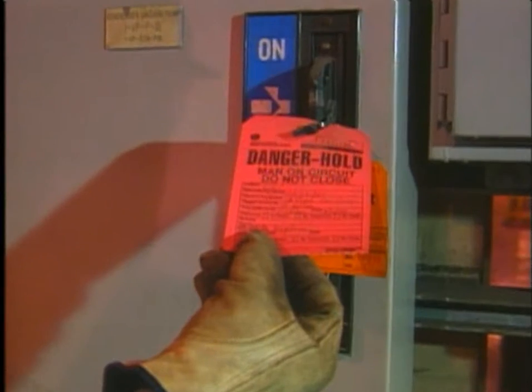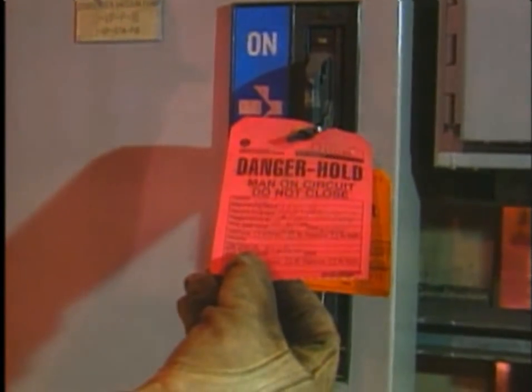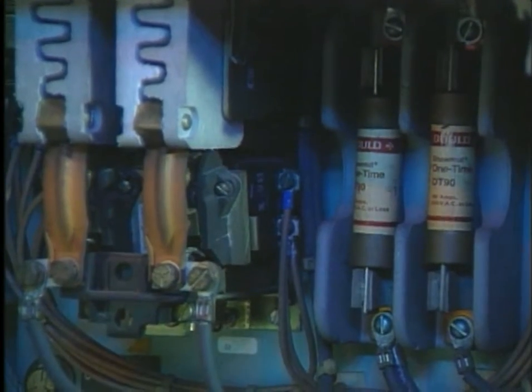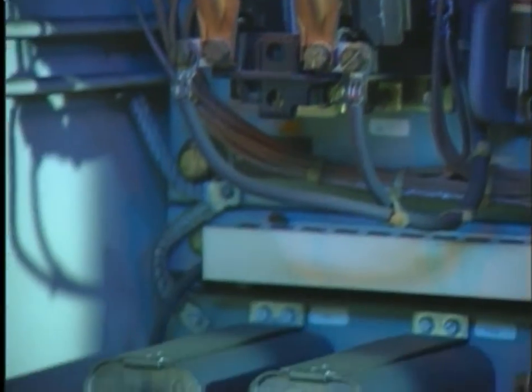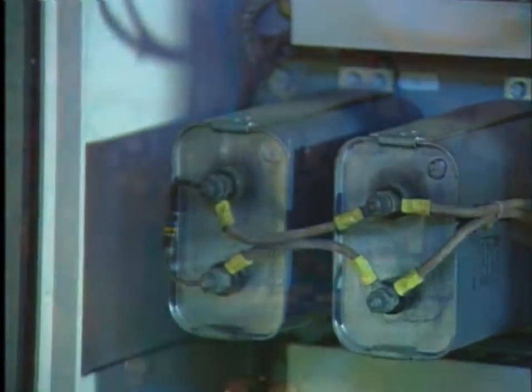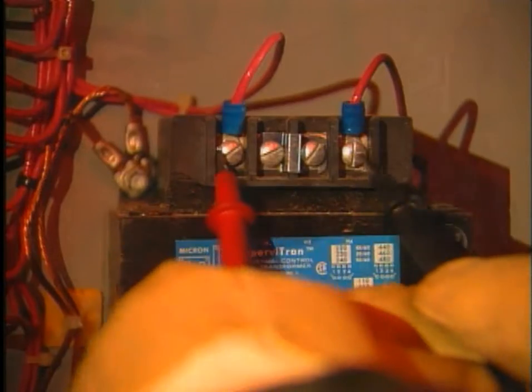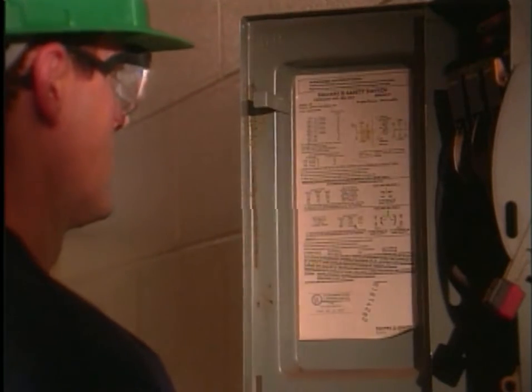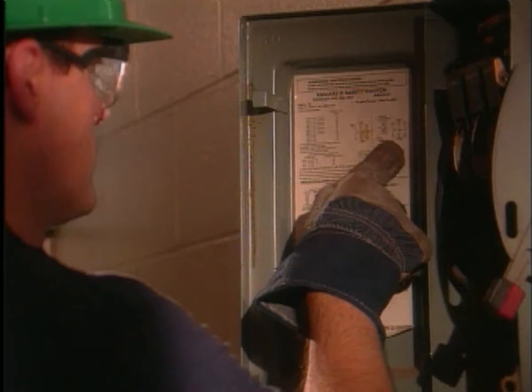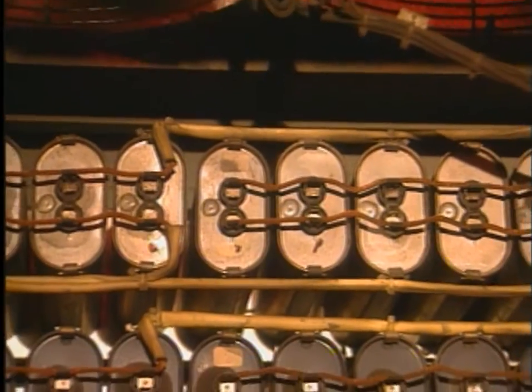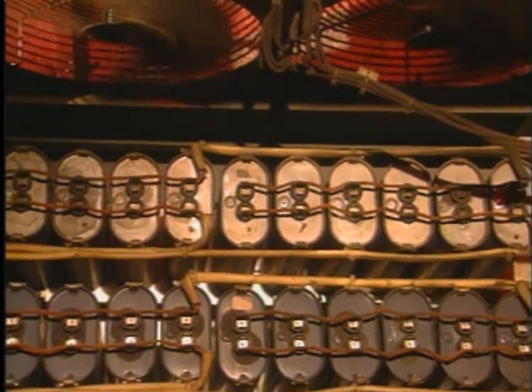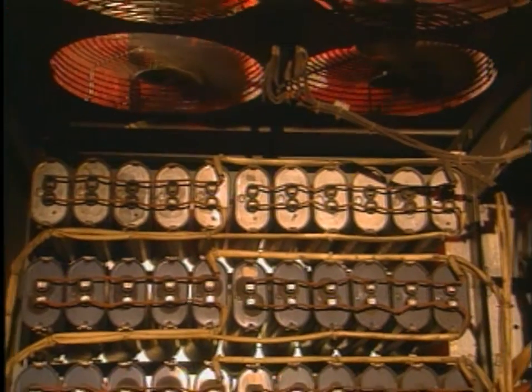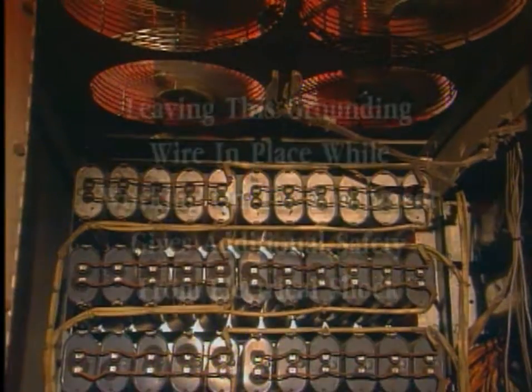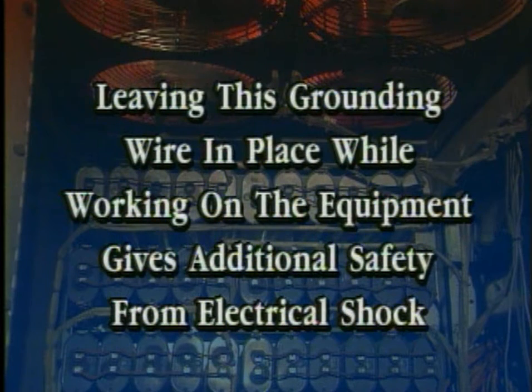Check to see that all power sources are controlled. Never try to find out if there's voltage left in a disconnected circuit by touching the equipment. Proper test equipment must be used. Look for capacitors and other forms of stored energy. To discharge capacitors, a grounding wire is connected between the capacitor and a known grounding source. Leaving this grounding wire in place while working on the equipment gives additional safety from electrical shock.